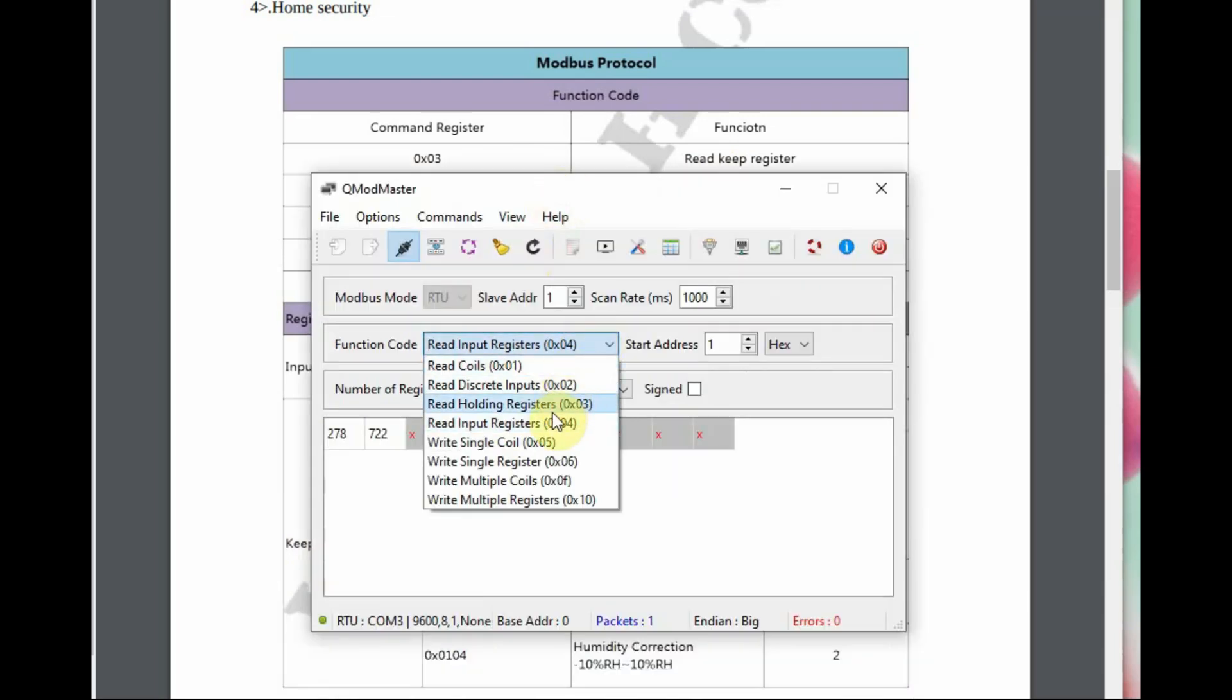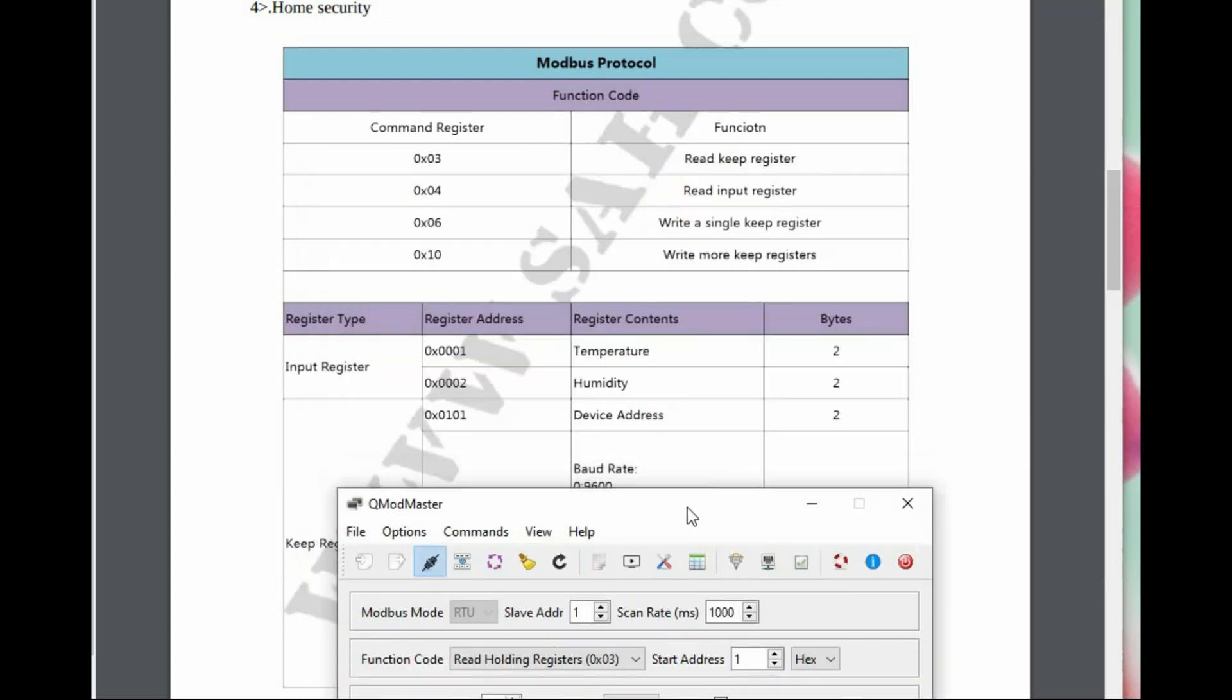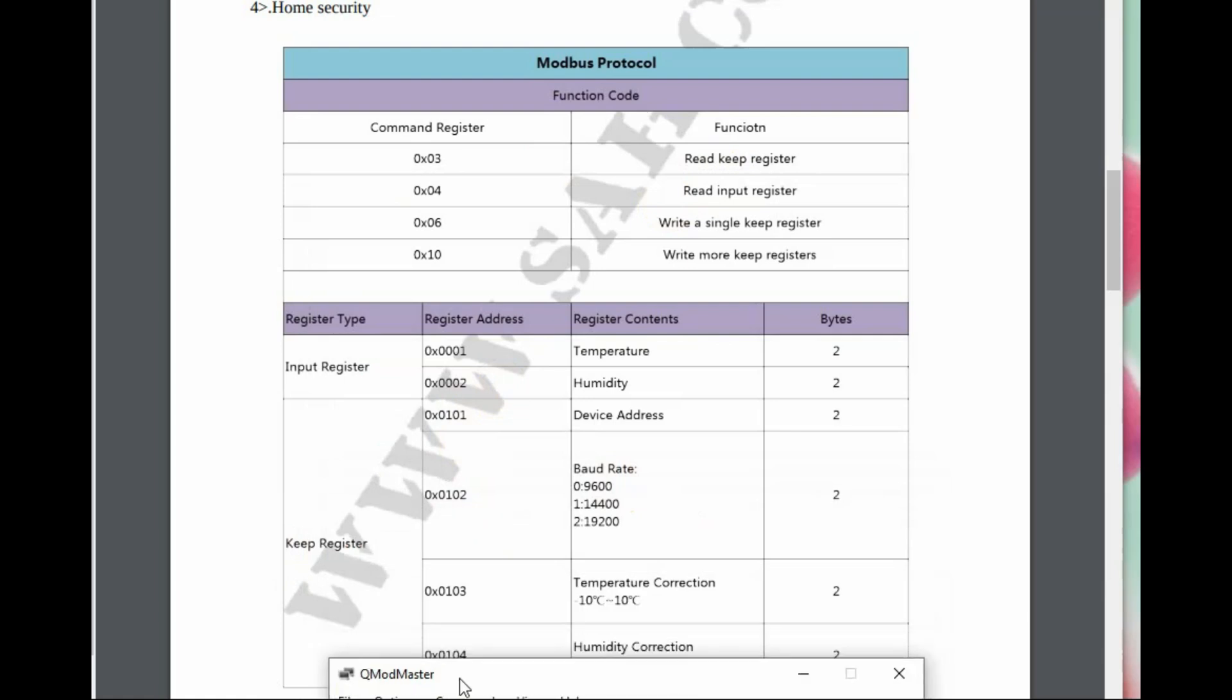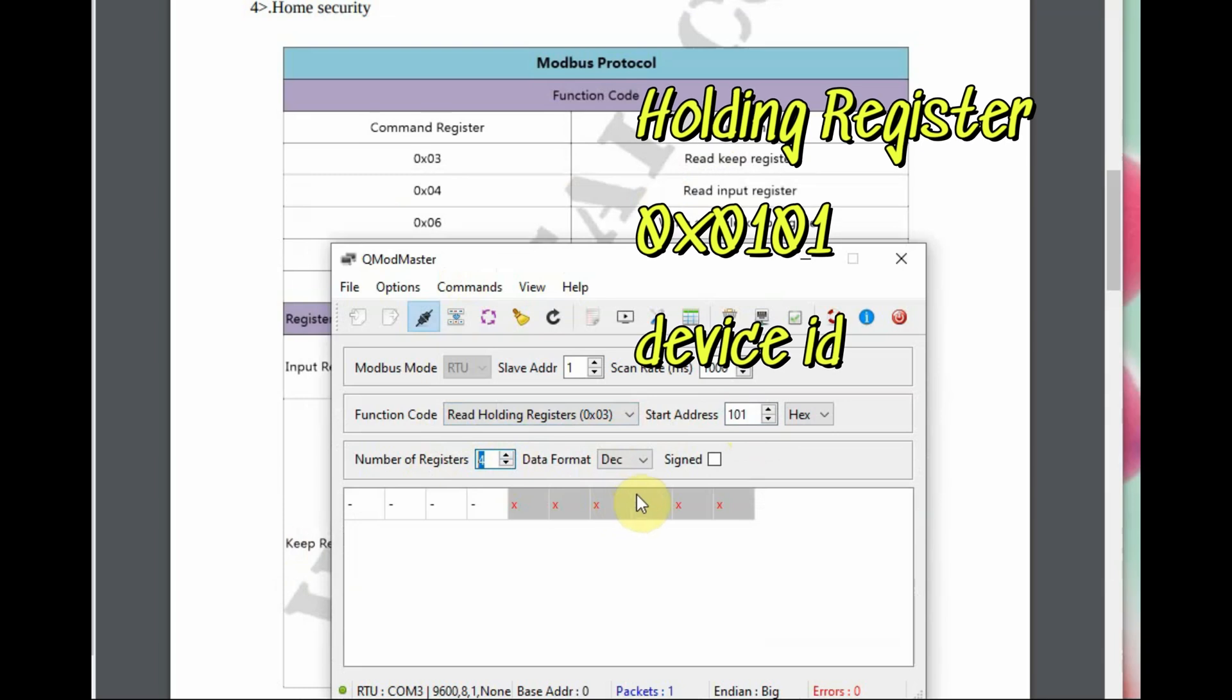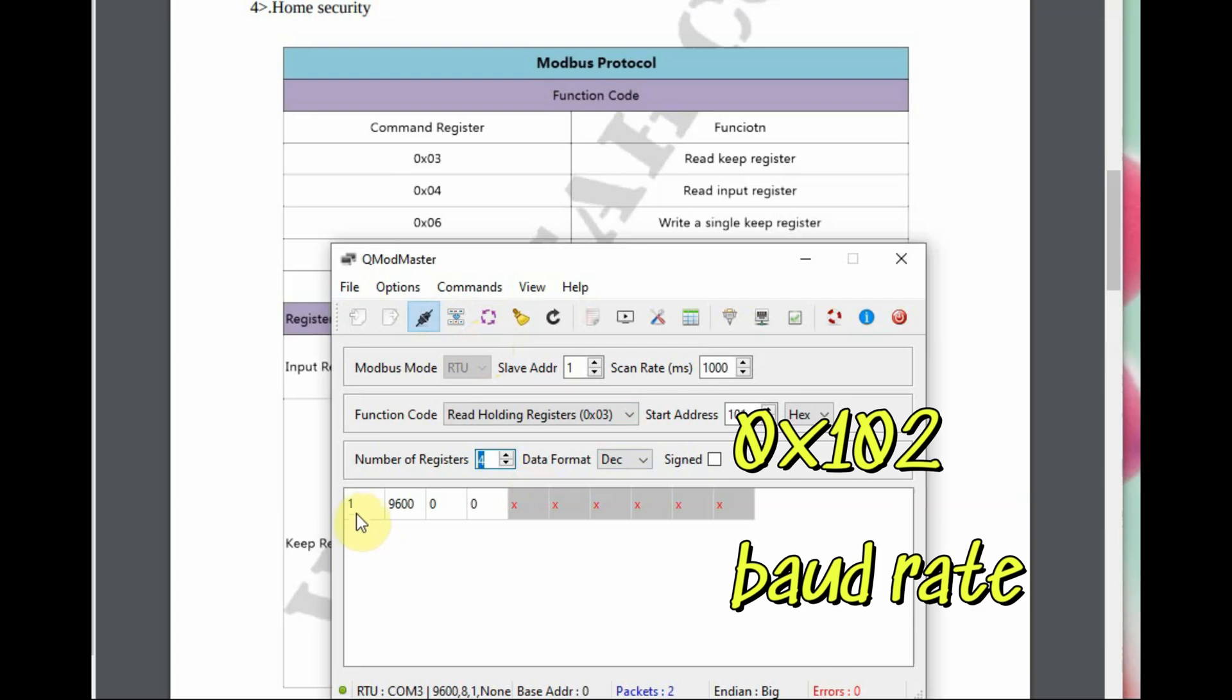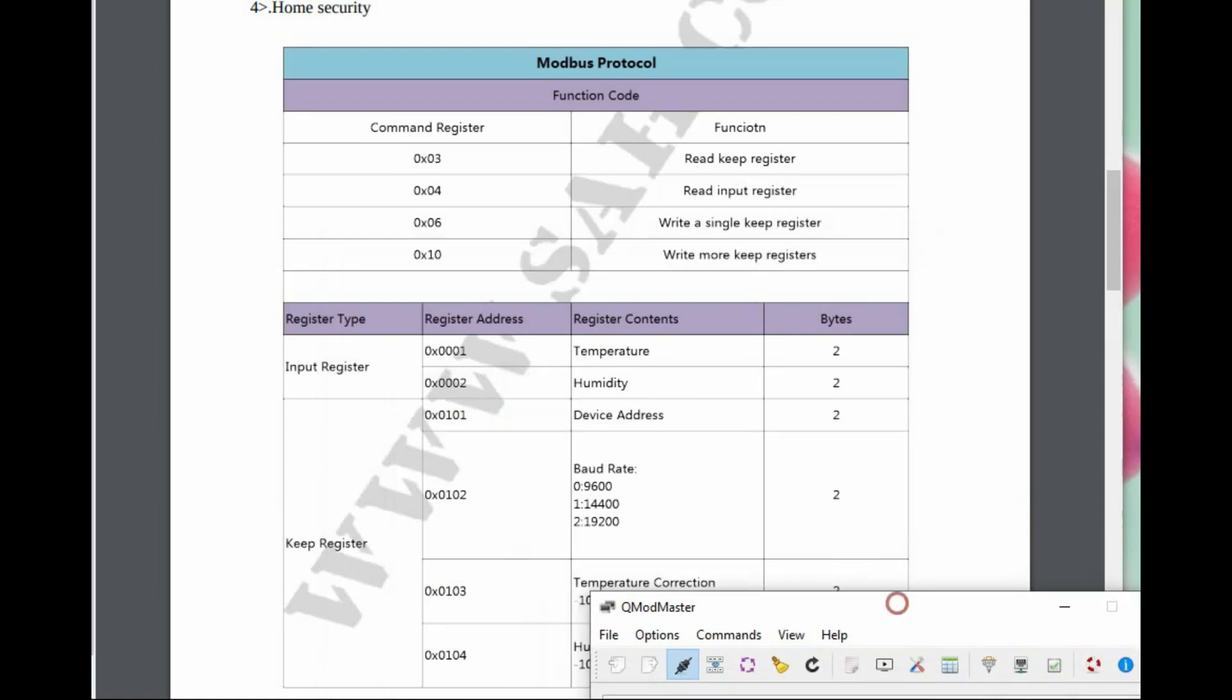To read these, we will be using the read holding registers, also called keep registers. Address 101 is for device ID, 102 is for baud rate. You can see the device ID is 1 and baud rate is 9600. Correction is 0, 0 for temperature and humidity. If you want to change the device address or baud rate, you have to use the 0x06 or 0x10 command.